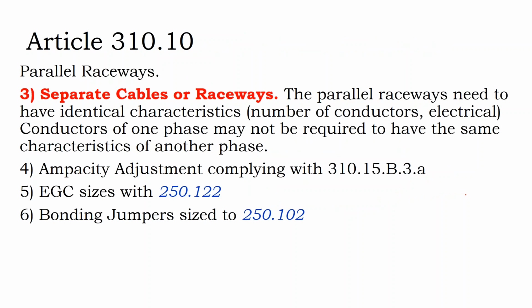In parallel raceways, the main requirement when you're doing parallel wire runs is that parallel raceways need to have identical characteristics. So if you take a raceway that would call for a 250 kcmil conductor, and you say, well, I want to do parallel wire runs so I can go down to a 4/0 cable size, and I want to do 2 parallel runs of 4/0 instead of 1 run of 250, that's fine, but they have to have parallel characteristics, and that means they have to have the same conductors. Your grounding conductor has to go through them. Your neutral conductors have to go through them, and they have to be the same size as well. They have to be identical.